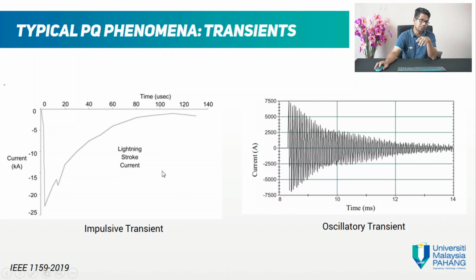That's why it's called oscillatory transient. So normally an impulsive transient is very big. For this example, from a lightning stroke, up to more than 20 kiloampere, okay, but very short time, in microseconds. While the oscillatory transient, this specific example is because of capacitor switching. So whenever we switch a capacitor bank, we will have this kind of waveform. Okay, so it oscillates. And one of the parameters of this oscillatory transient is the frequency of the oscillation itself.